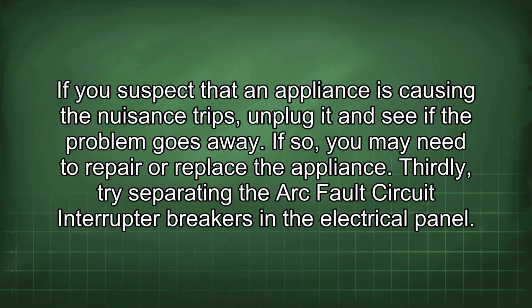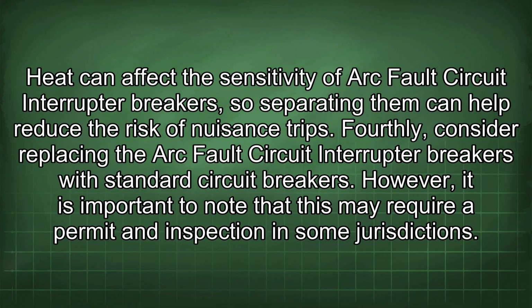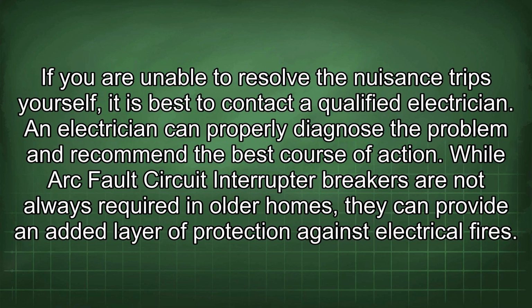Thirdly, try separating the arc fault circuit interrupter breakers in the electrical panel. Heat can affect the sensitivity of arc fault circuit interrupter breakers, so separating them can help reduce the risk of nuisance trips. Fourthly, consider replacing the arc fault circuit interrupter breakers with standard circuit breakers. However, it is important to note that this may require a permit and inspection in some jurisdictions. If you are unable to resolve the nuisance trips yourself, it is best to contact a qualified electrician. An electrician can properly diagnose the problem and recommend the best course of action. While arc fault circuit interrupter breakers are not always required in older homes, they can provide an added layer of protection against electrical fires.